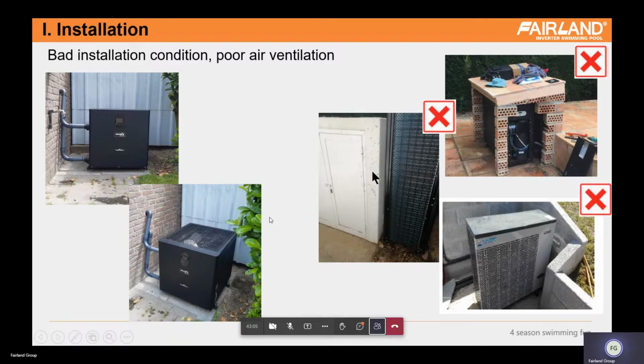And like this one, it's a new unit from a customer in Portugal. The heat pump is new and installed very close to the wall, because, as the customer said, the garden is a little small, so there was not enough space. For this one, the compressor was damaged, so they had to replace the compressor. And for this one, it's better. It's just affecting the heating capacity, so maybe it will take a longer time to reach the desired pool temperature. Just need to move the unit. So the installation space is very important.